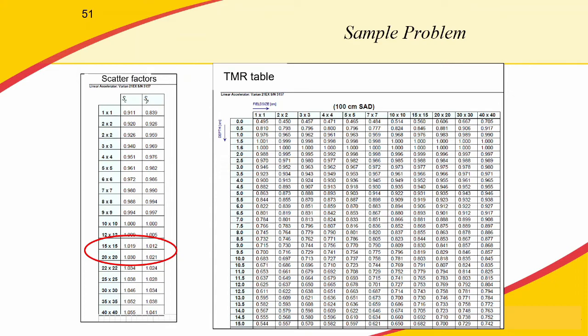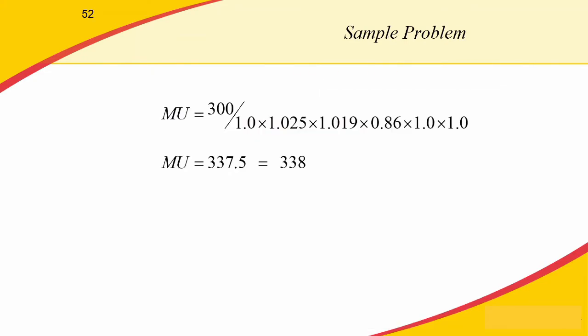Then we go to our TMR table, since we're set up and delivering isocentrically, and we assume calibration was done isocentrically. Again, we have 15 by 15 and 20 by 20 field sizes in our table. We scroll down to 8 cm depth for our calculation, where we have values of 0.855 and 0.863. We interpolate between those to get our TMR value of approximately 0.86, then plug those into our equation.